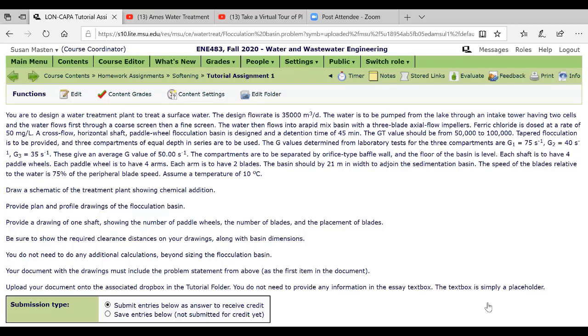So what I've given you is the specification. So in this case you're told that you're designing a water treatment plant to treat a surface water. Designed flow rate is in this case 35,000 cubic meters per day. The water is to be pumped from a lake through an intake tower having two cells and the water flows first through a coarse screen and then a fine screen. The water then flows into a rapid mix basin with three blade axial flow impellers. So you've got to think about what this means.